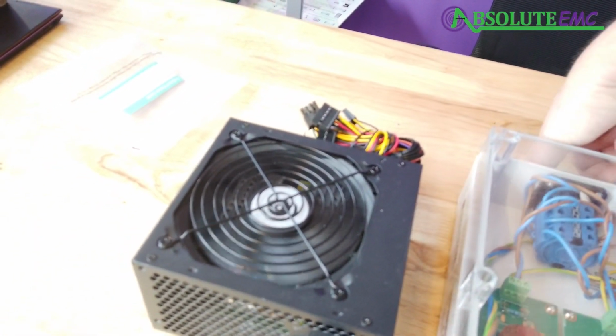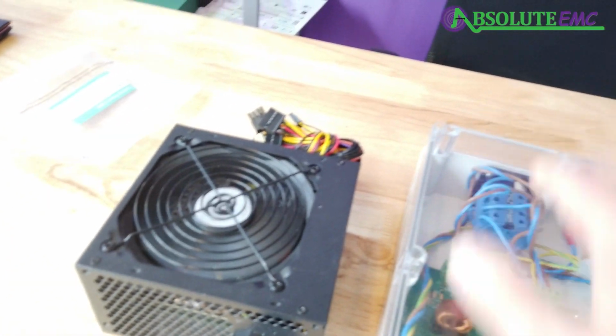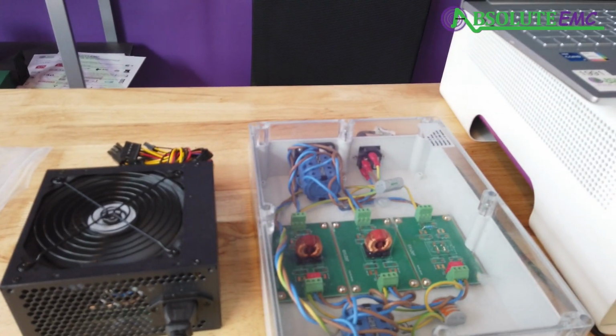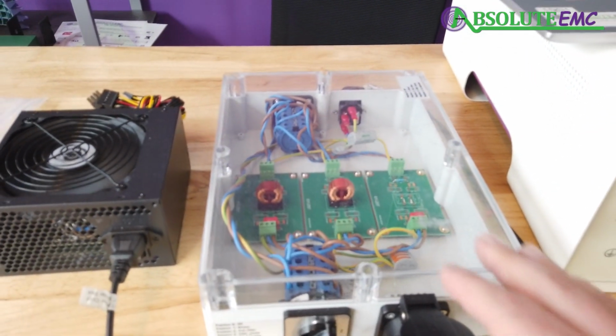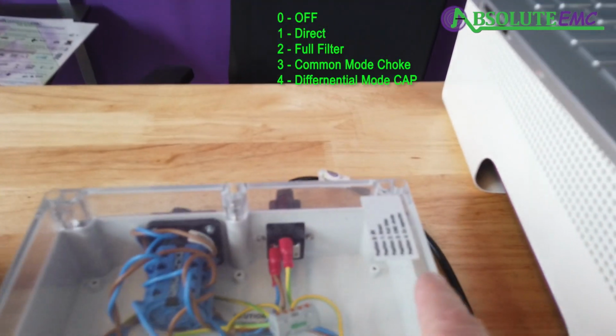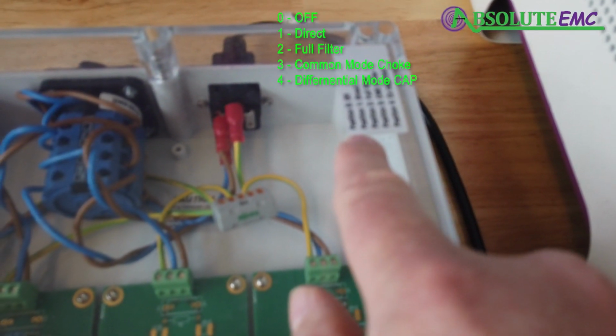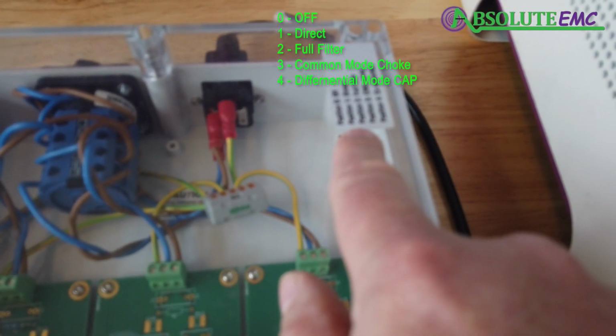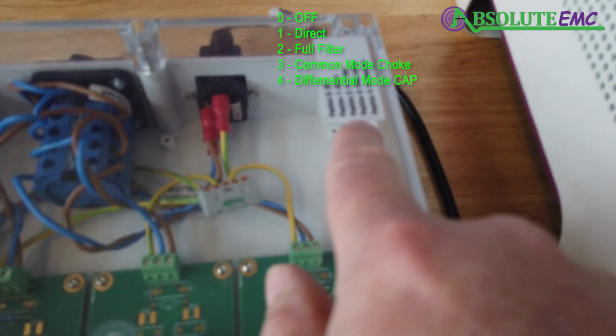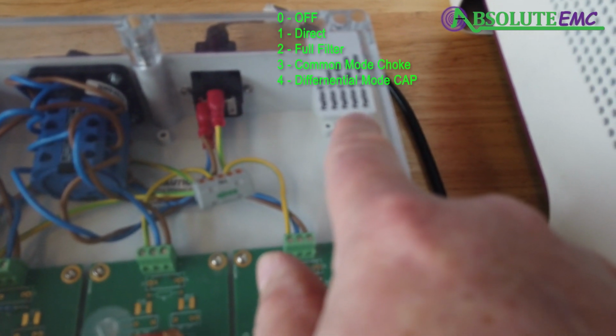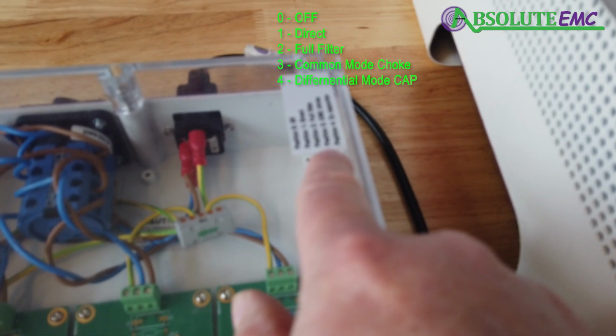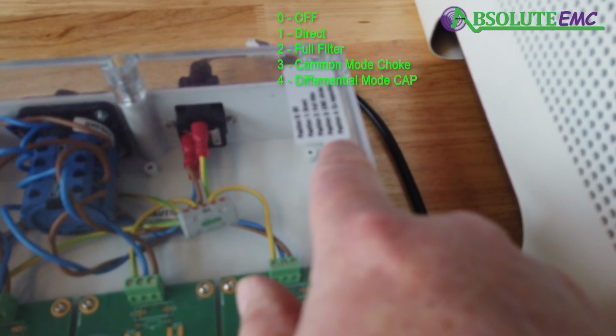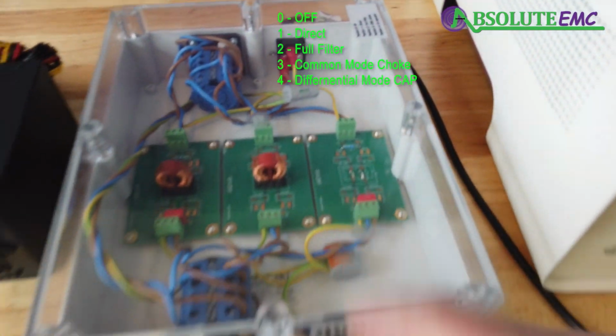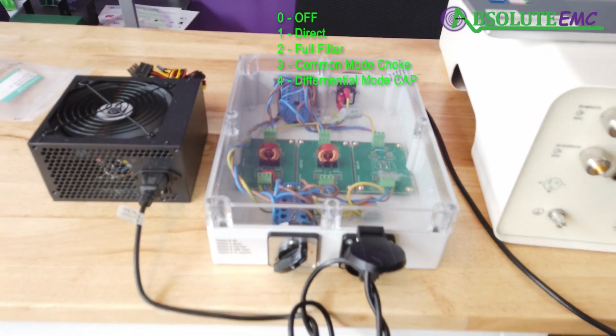We have different switches here. And go to the start here. So this is a straight pass-through measurement. So if we look here, position zero is off. Right now I'm in position one, which is direct. There's no filtering. Position two is a full filter. Position three is CMC choke. And position four is a capacitor that goes between the two lines.